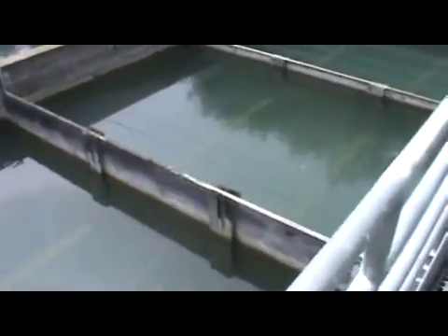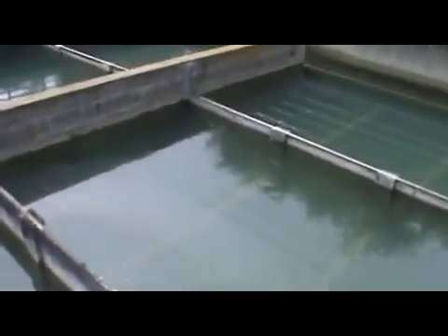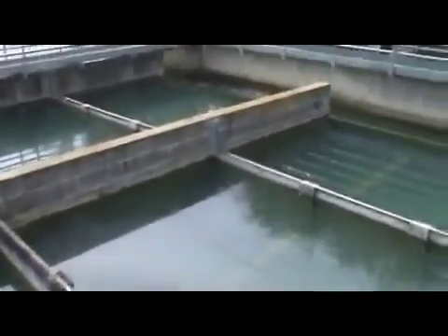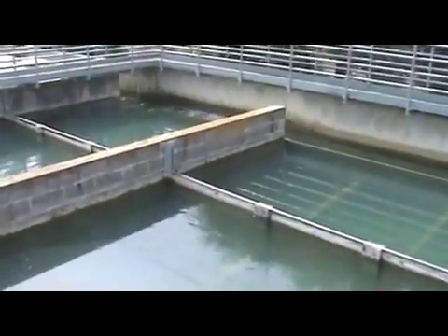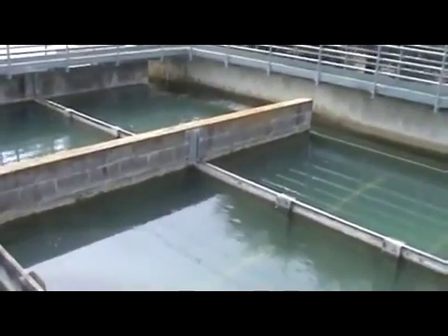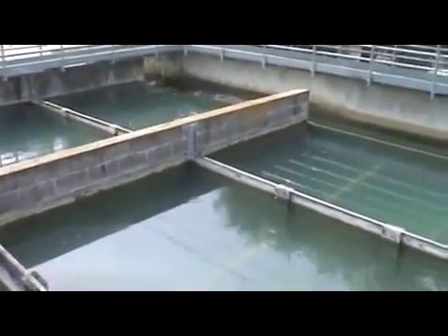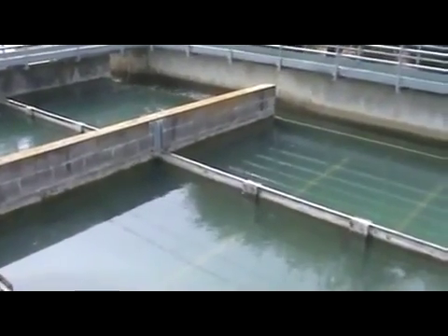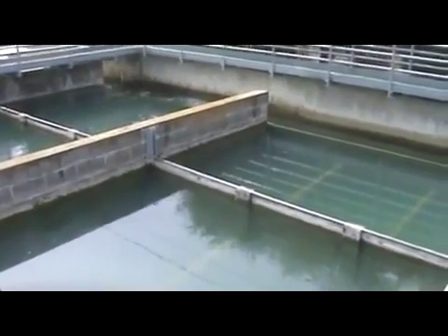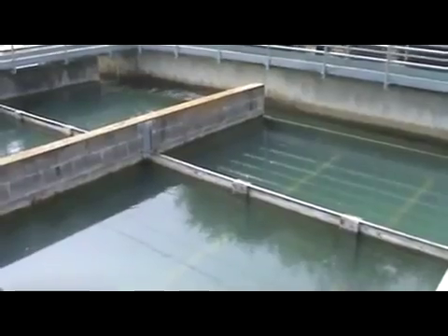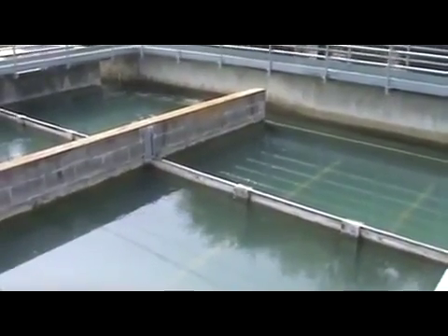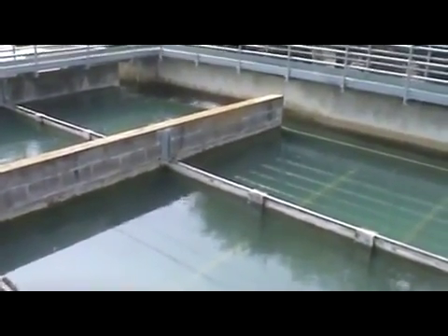The detention time of the water passing through these flock basins is generally about 15 to 45 minutes. Now that depends on the flow. This particular plant has a 30 million gallon capacity. Right now it's flowing about 11 million gallons of water through it, so it's not really ripping at high speed right now. So you're going to have a little longer detention time going through these flock basins here.